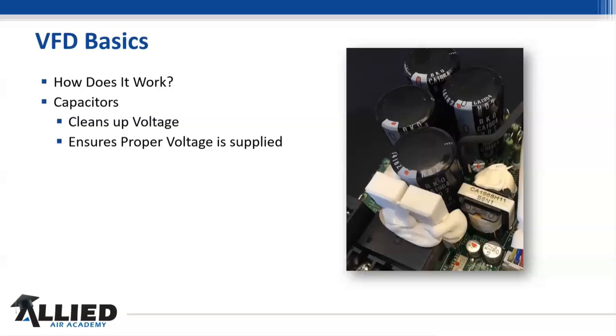But the capacitors also operate much like an accumulator does in a refrigeration system. It can hold and store some voltages as well. It's going to absorb the AC ripple, and it's going to deliver a smoother DC voltage. So that AC ripple on DC is typically less than 3 volts, but it does have a ripple in there. And the actual voltage is going to depend on the level of the AC feeding the drive as well. And that kind of makes sense.